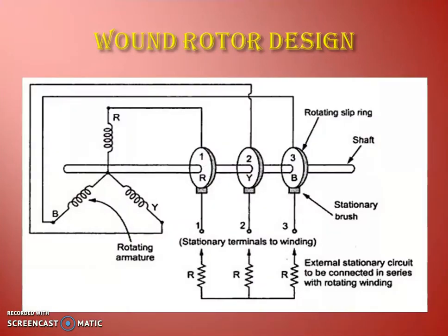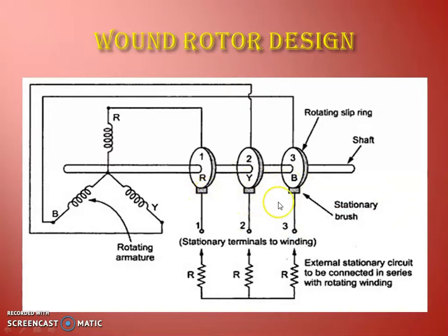The rotor winding is normally connected in star. One end is connected at the star point and the three windings are taken outside and connected to the slip rings — three slip rings. On the other side, brushes are connected and external resistance can be connected to the slip rings and through the slip ring it can be connected to the rotor winding.